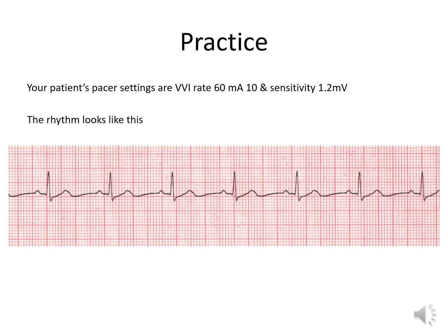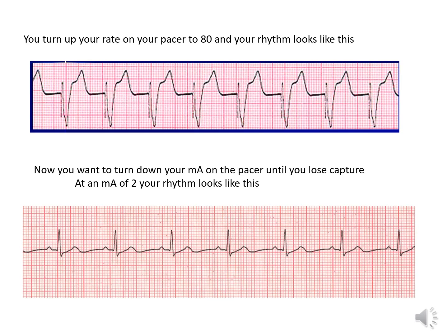Okay, so let's practice and look at it with the actual strips. Here your patient's pacemaker settings are a VVI of 60 with a MA of 10 and a sensitivity of 1.2 millivolts. The rhythm, as you can see here, looks like a beautiful normal sinus rhythm. Now we are going to turn the pacemaker rate up to 80. When we do that, you can see that you're 100% paced. Then we leave it at a rate of 80.